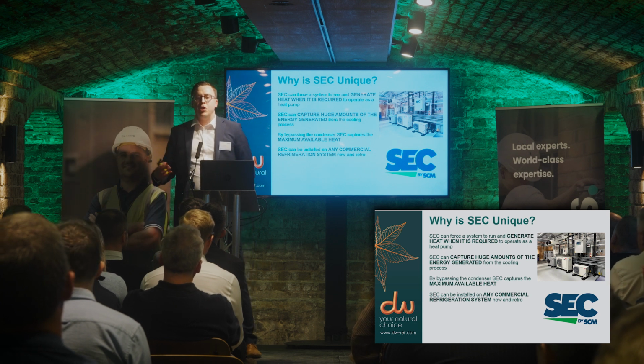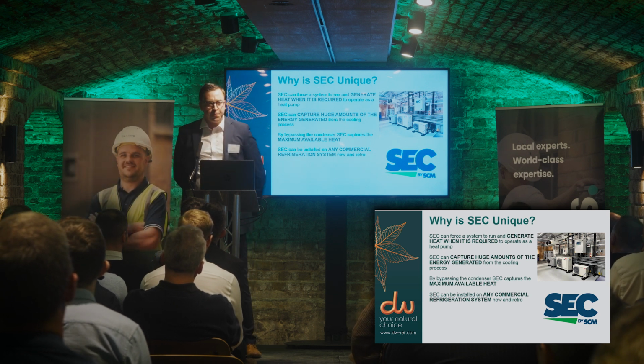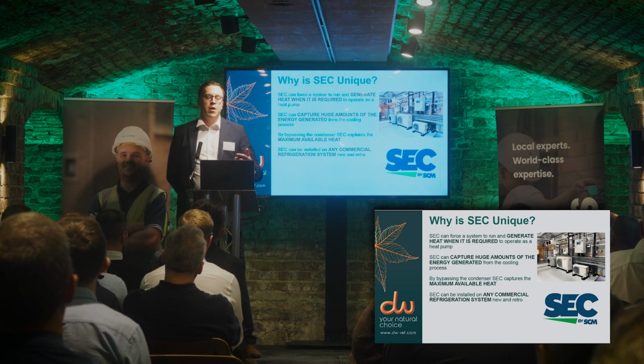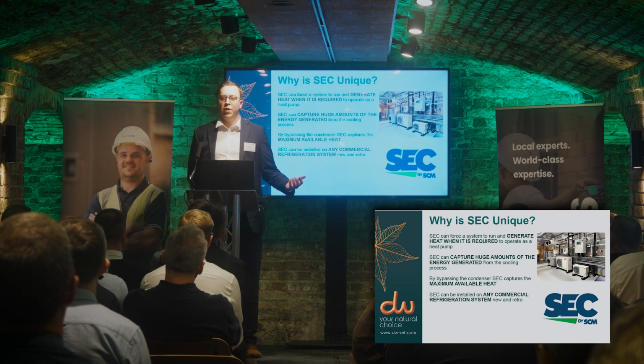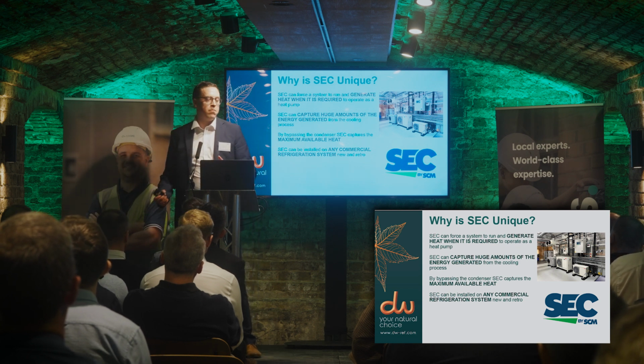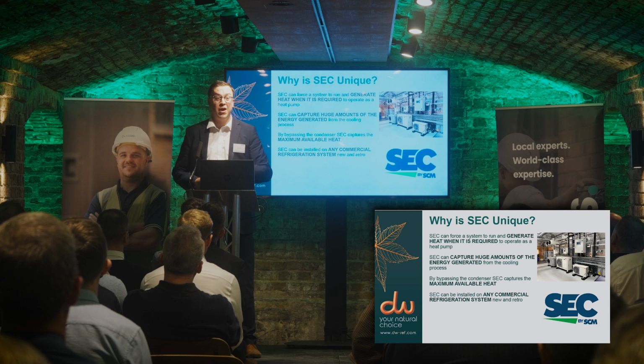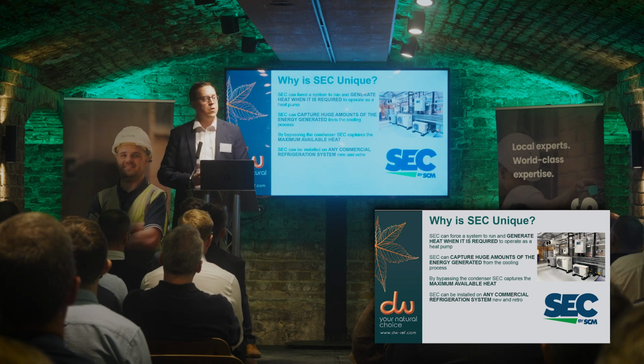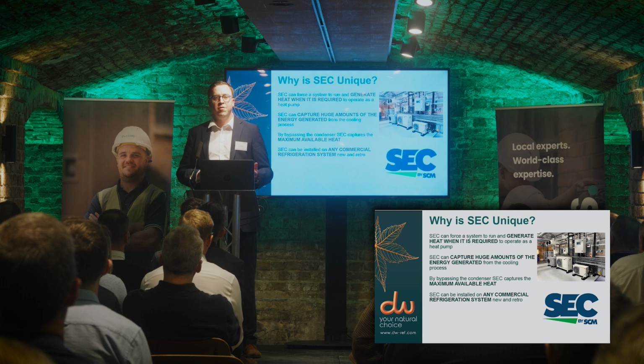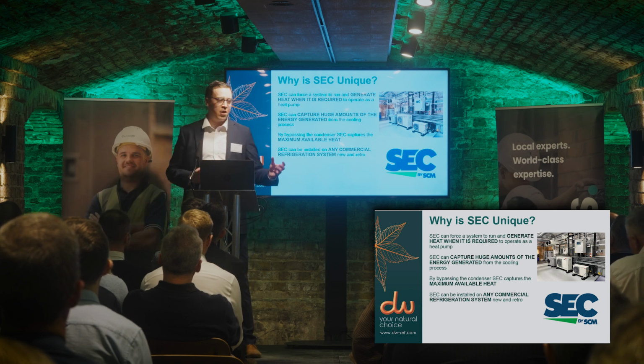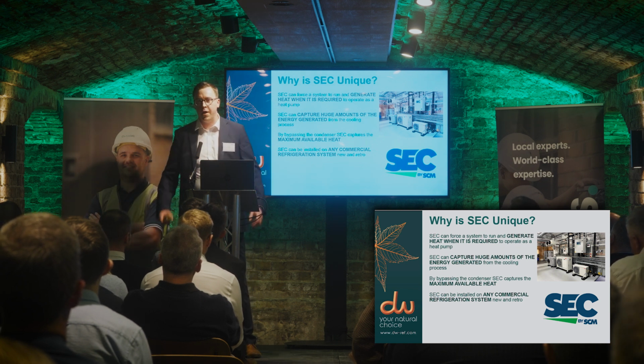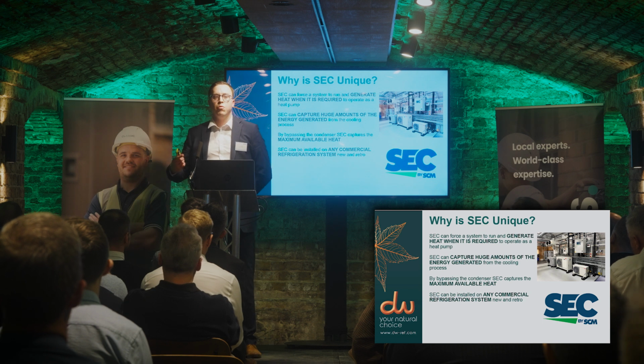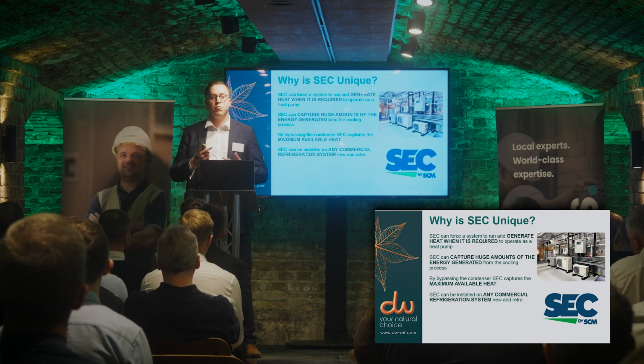I said the technology is unique. Why is it unique? Typically, heat recovery will only occur if you've got a cooling demand. So in the summer, your refrigeration equipment, your AC equipment will be running flat out, and you'll get lots of heat as a byproduct. In the winter, that's completely opposite. Your fridge kit's hardly running, and therefore you're not going to get any heat. What SEC will do is almost force the system to run like a heat pump.